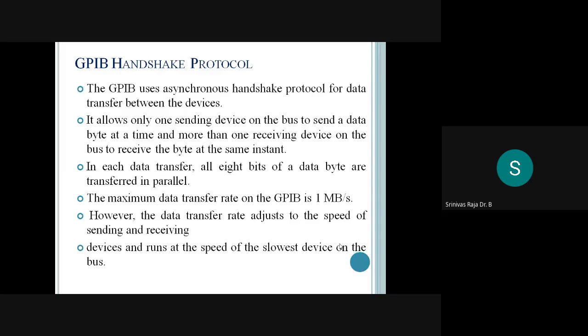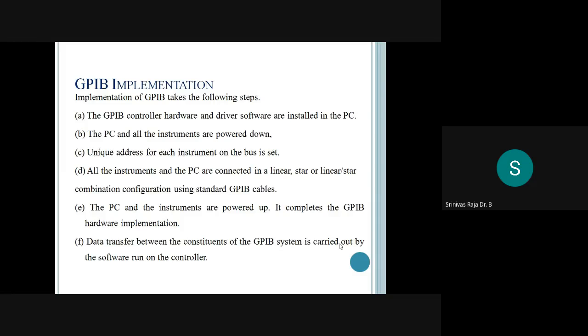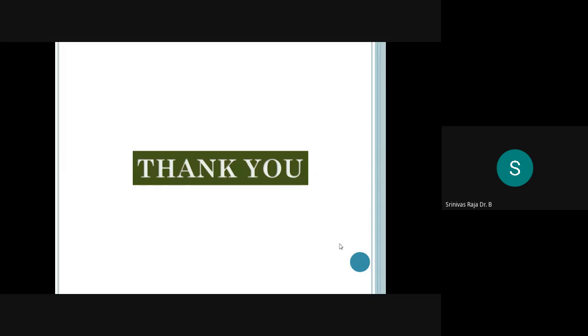This shows how to interface devices to the personal computer using a GPIB interface card. The GPIB controller hardware and driver software are installed in the PC. A unique address for each instrument on the bus is set. All instruments and PCs are connected in a linear or star combination using GPIB cables. The PCs and instruments are powered up, hardware implementation is completed, and data transfer between the GPIB system is performed using software.